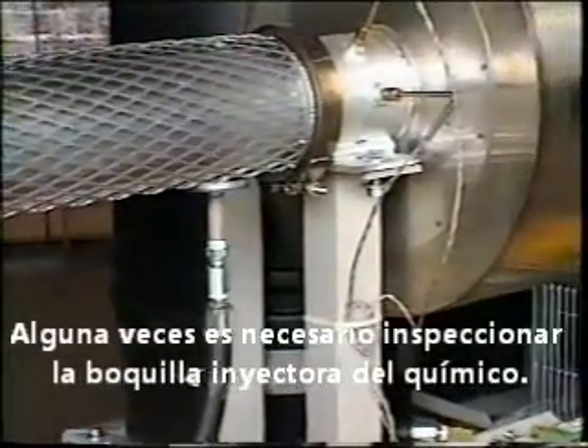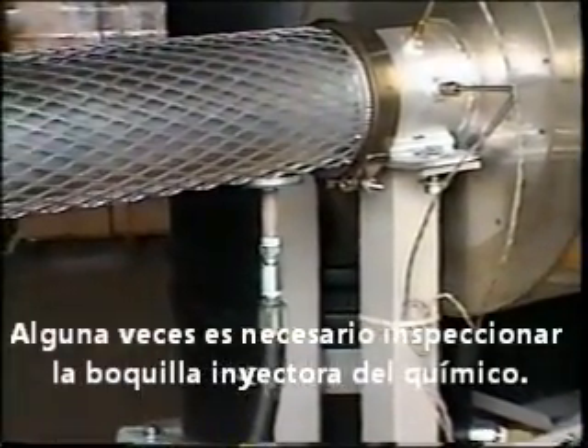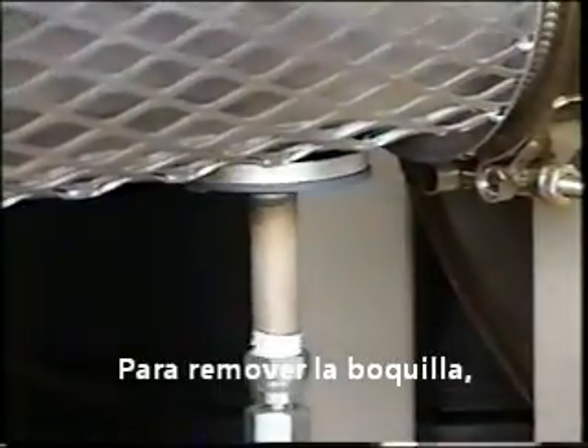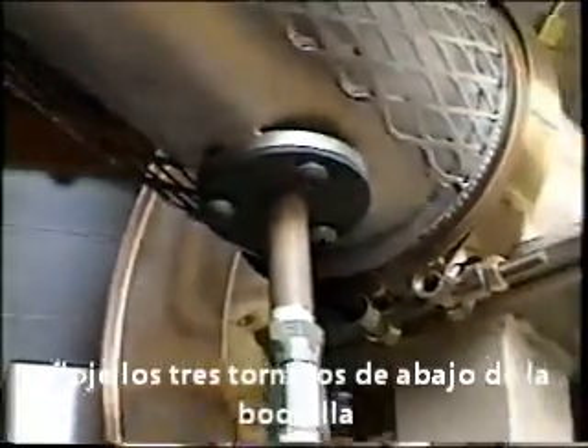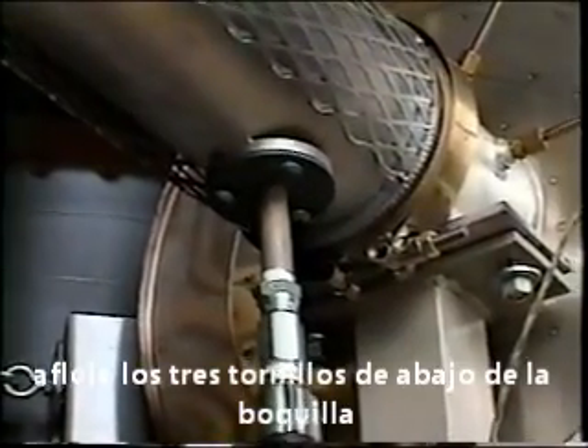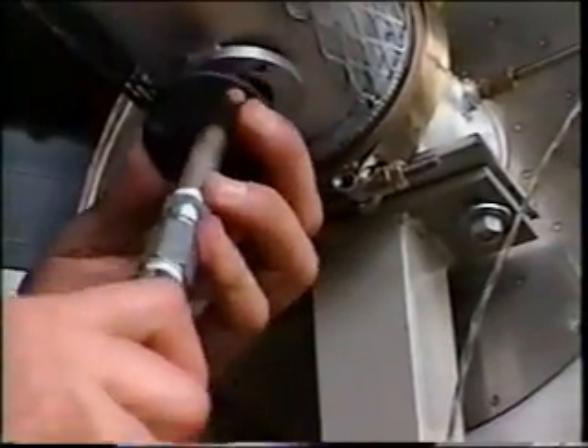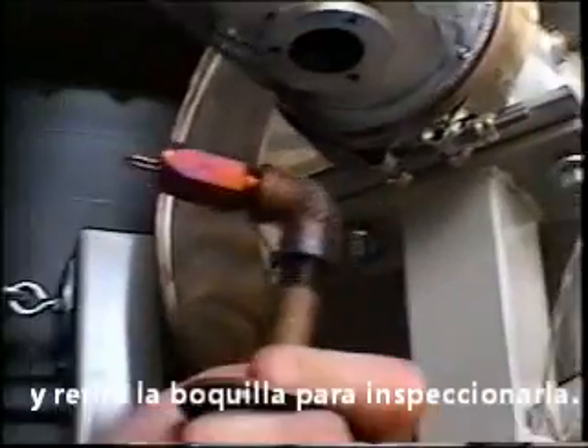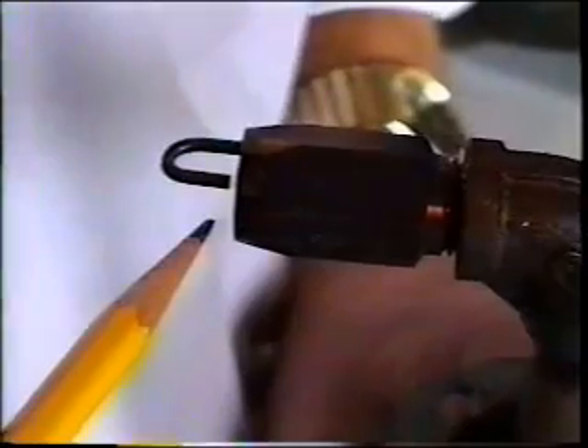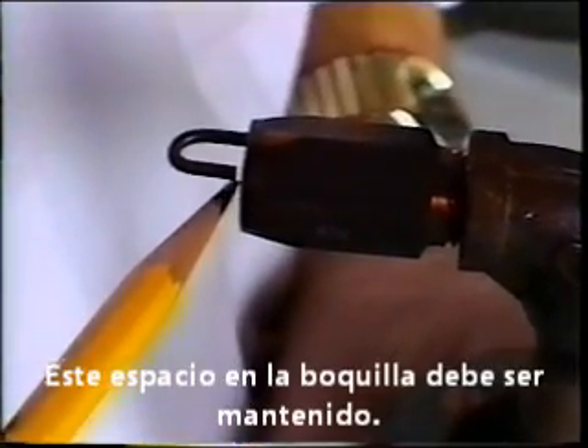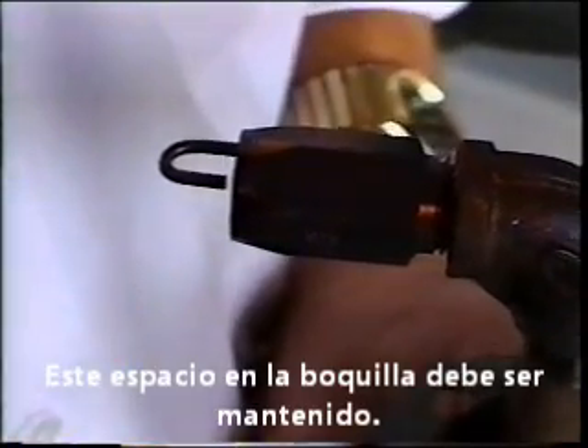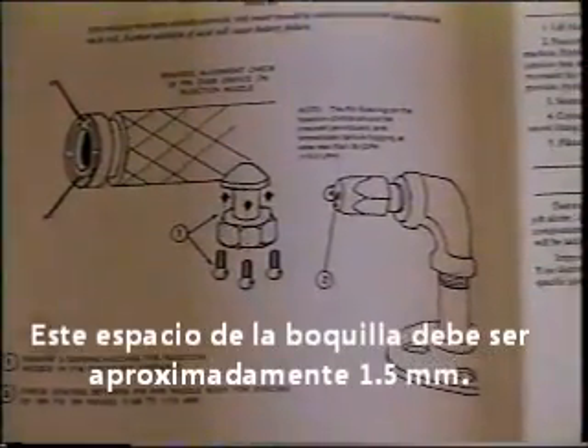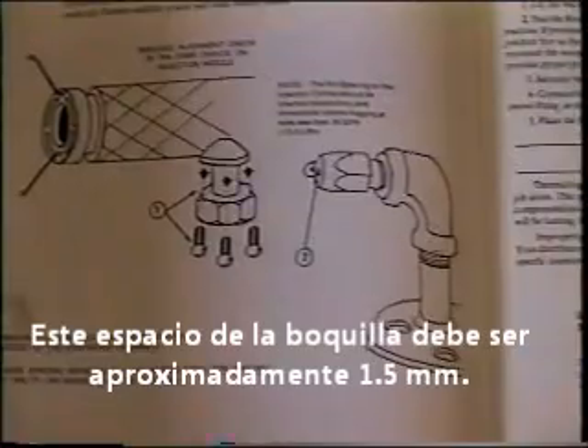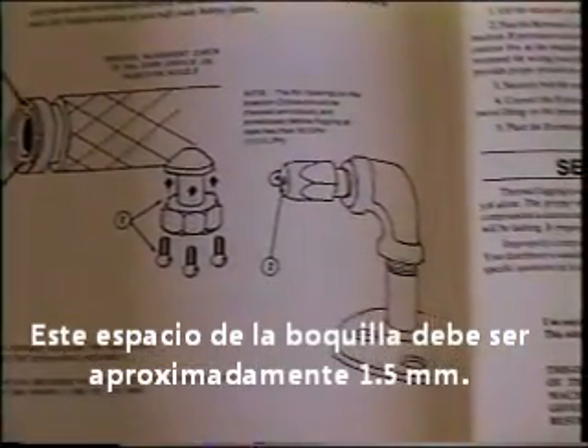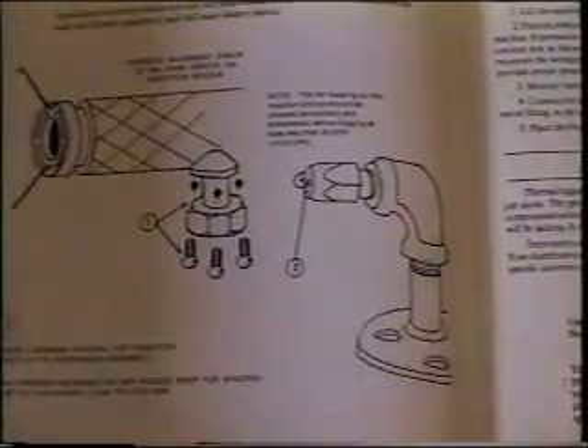Sometimes it is necessary to inspect the chemical injection nozzle. To remove the nozzle, unloosen the 3 screws holding the nozzle into the tube, and the nozzle can be removed for inspection. This gap on the nozzle must be maintained. This nozzle gap is approximately 60 thousandths of an inch or 1.5 millimeter.